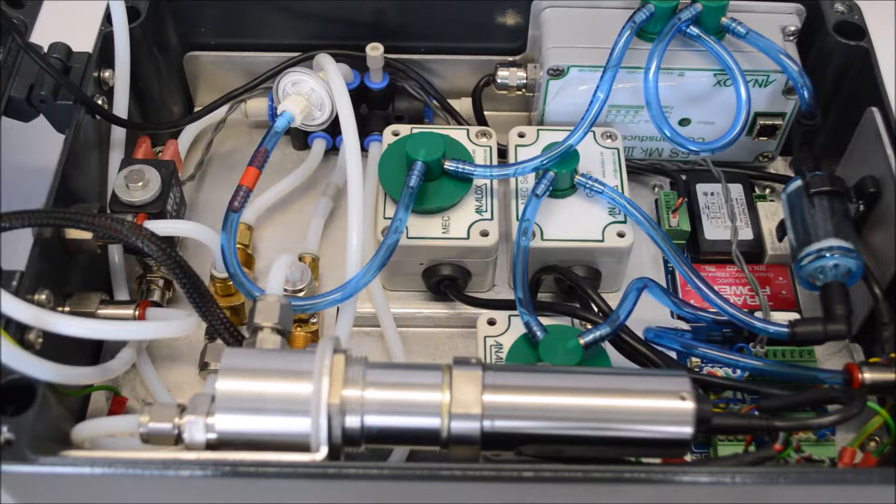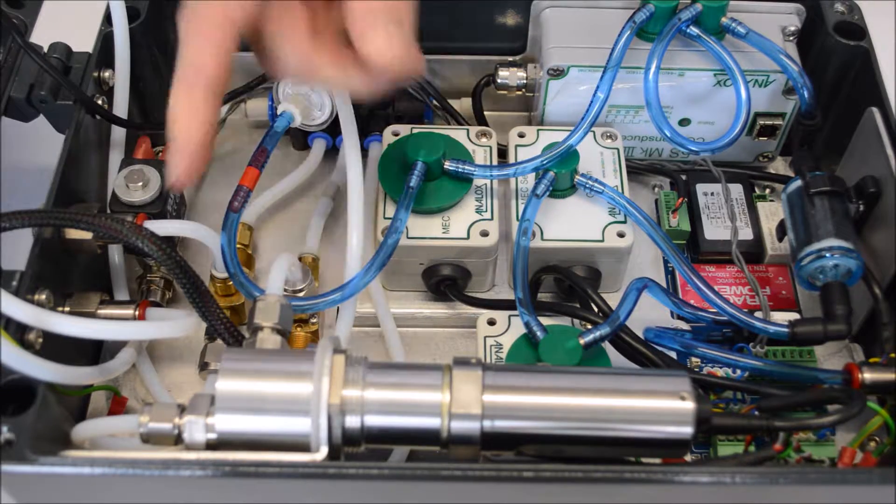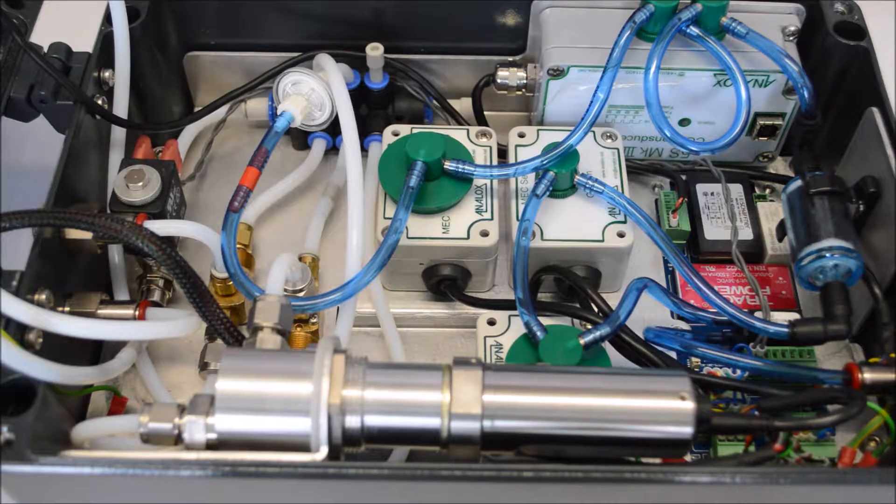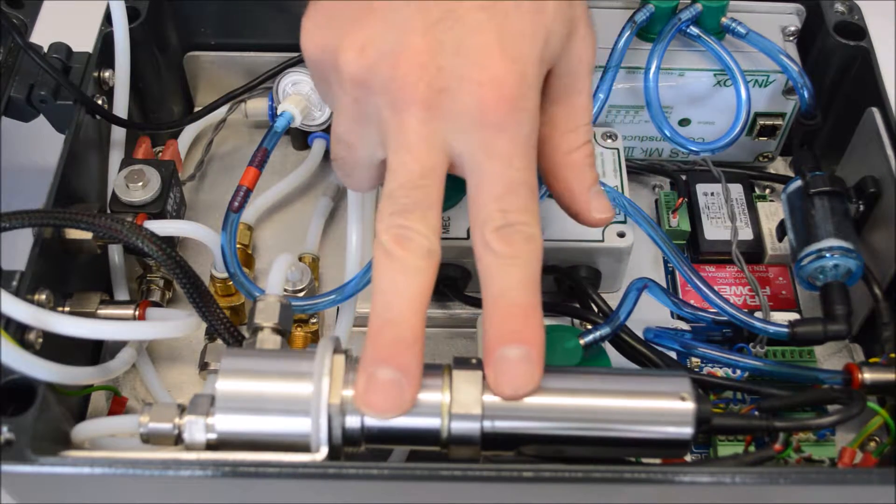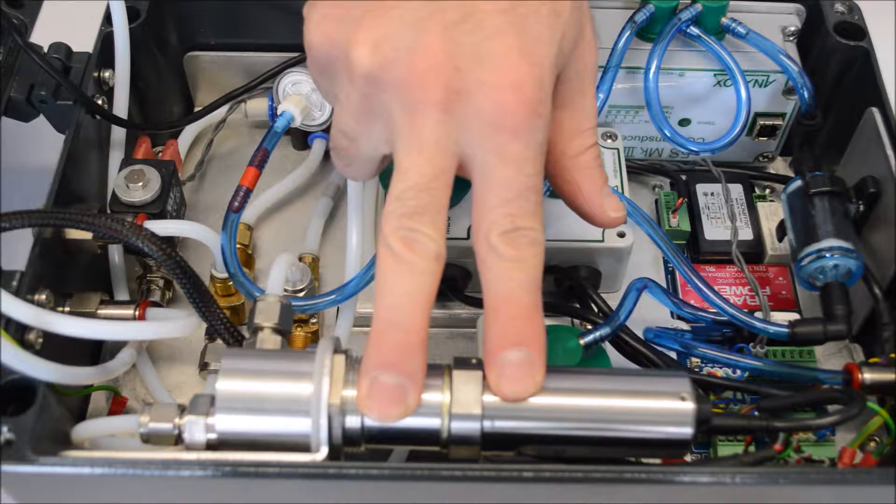This is now the maintenance activity to replace the dew point sensor. This sensor is the only sensor within the unit that can't be calibrated, so it gets replaced on a swap-out basis after two years.